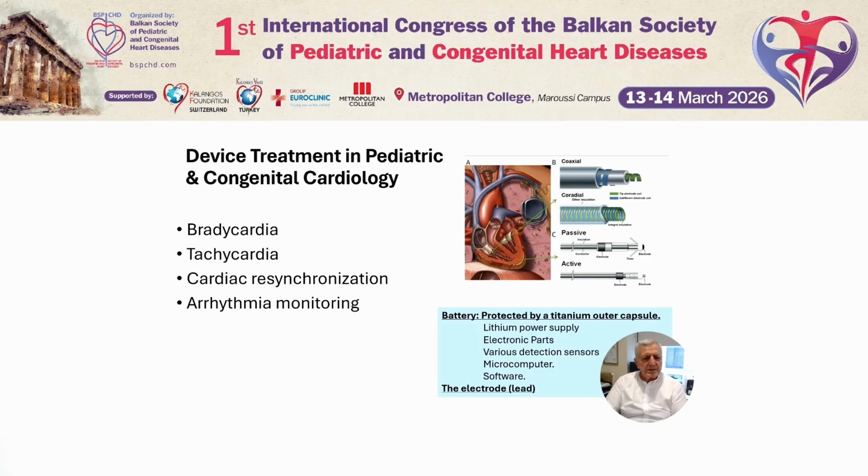For the indications for device treatments, bradycardia is the main one. It can also be used in tachycardia management, in cardiac resynchronization, and in arrhythmia monitoring. The system consists of two main parts. One is the battery, protected by a titanium outer capsule, with a lithium power supply, electronic parts, several sensors, a microcomputer and software. The other is the lead that conducts the impulse from the battery to pace the atria or ventricles.